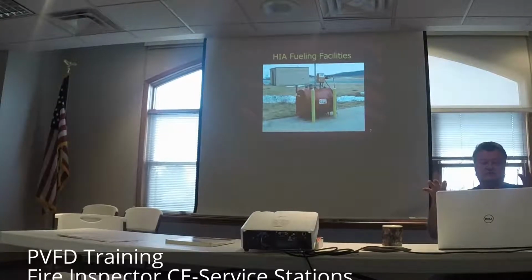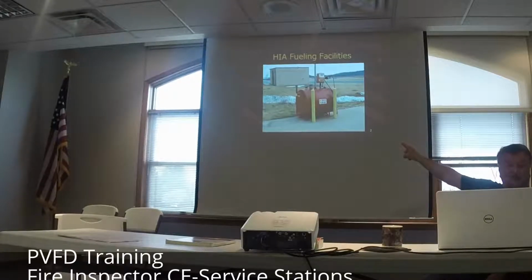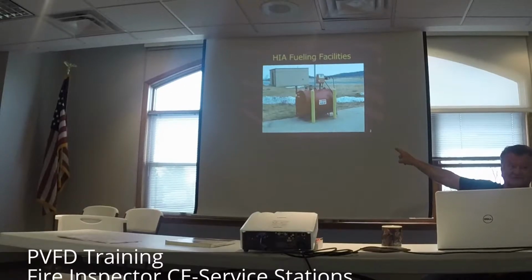What I gave you, and we went all over it, was the stuff that you got the codes for. Now I'm hoping to show you some things that you shouldn't have. This is on an Air Force base. You can see the plane back there in the corner of the picture, the tip of it. Now, does that look like it's protected? Yeah. It sits outside the deals, don't it?